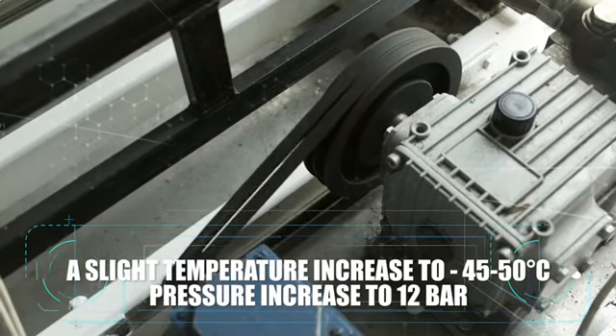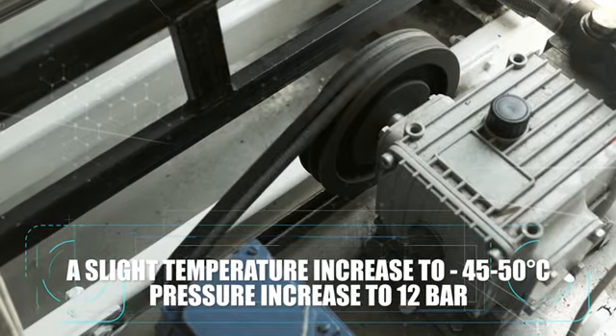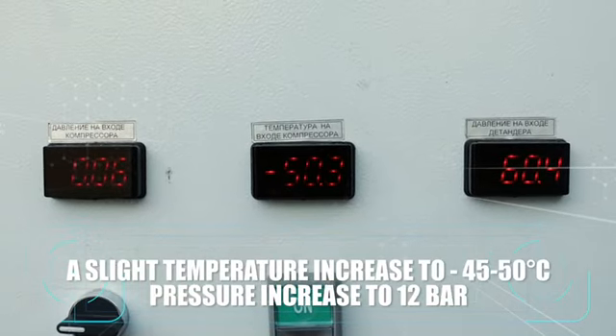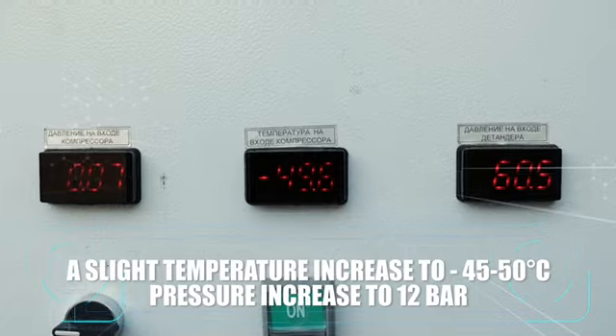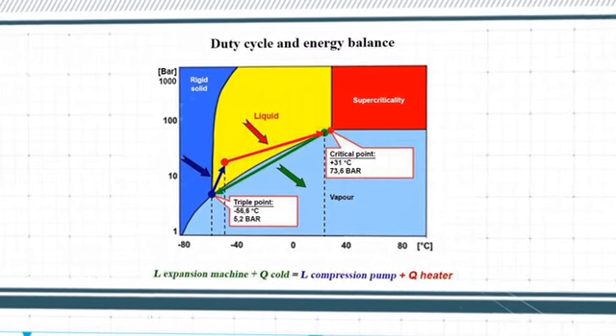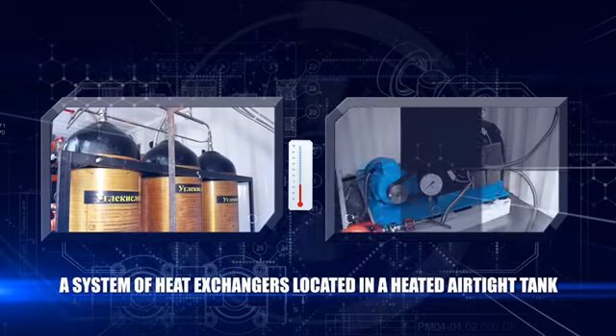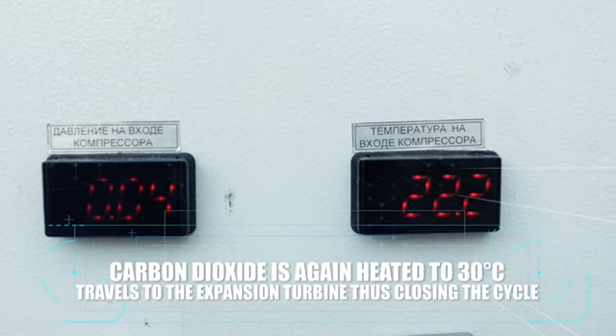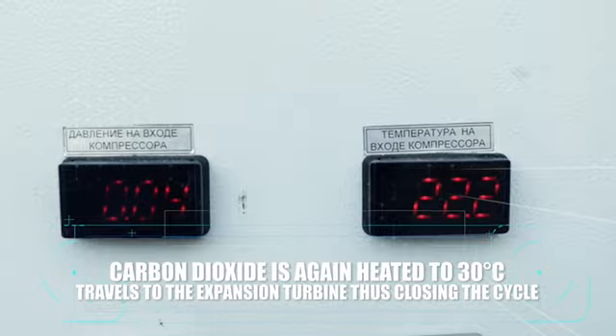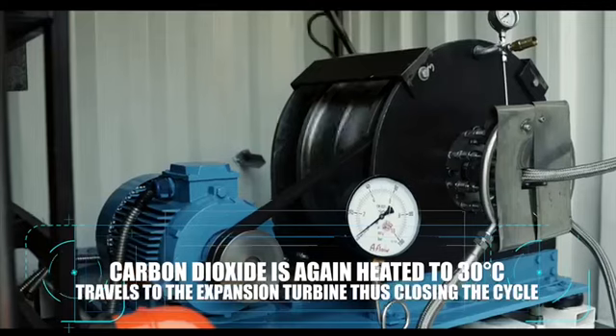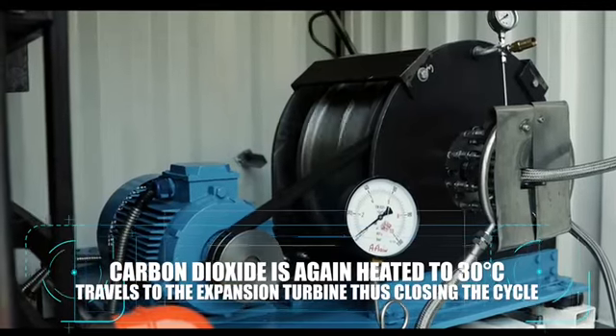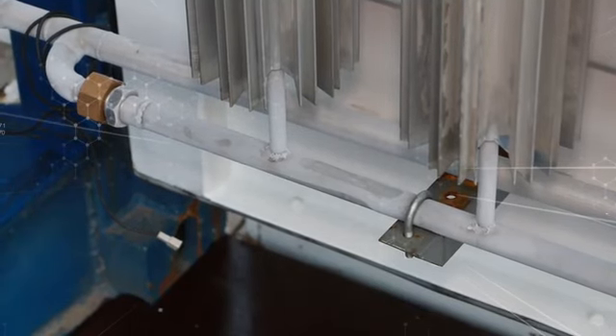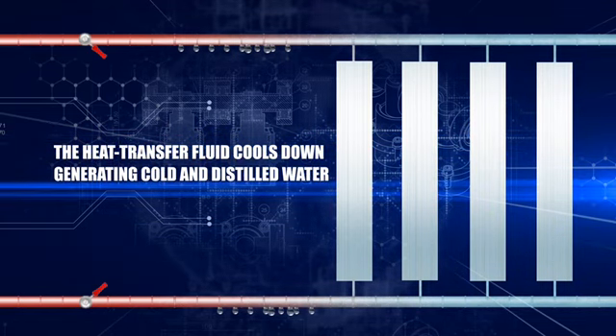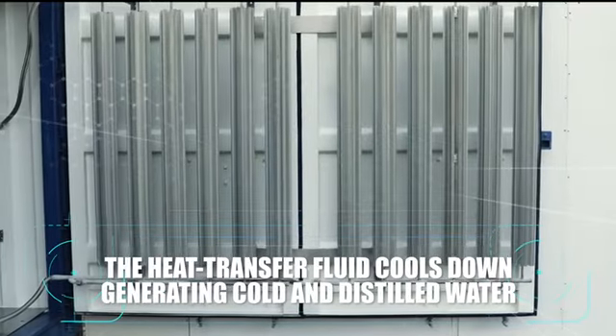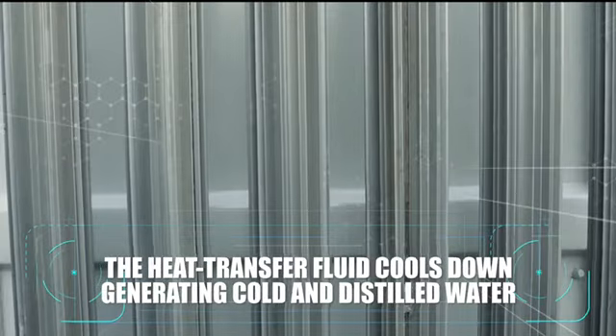The compression process results in a slight temperature increase to -45 to 50 degrees Celsius, and pressure increase to 12 bar. Liquid carbon dioxide then goes to a system of heat exchangers located in a heated airtight tank. Carbon dioxide is again heated to 30 degrees Celsius and travels to the expansion turbine, thus closing the cycle. The heat transfer fluid, for example water and anti-freezing agent, cools down and is discharged to the external heat exchanger system for generating cold and distilled water in the form of a condensate.